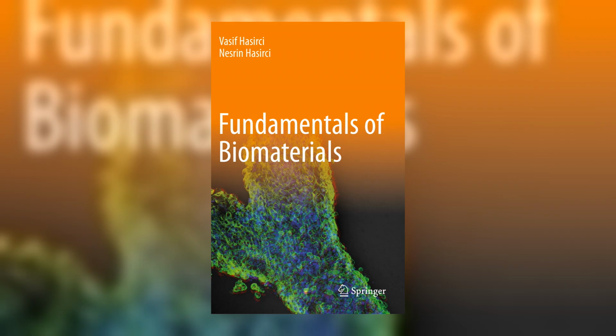Its job is to decide whether degradation must be characterized at all, and to structure that decision before the material-specific parts, polymers, ceramics, and metals actually quantify what comes off. The move is to split one question into two gates, so screening precedes measurement. The first gate asks, does it degrade under use conditions? The second gate asks, what does it release, and is that dose toxic? Everything downstream in the series is this router, dispatching to a material's chemistry.